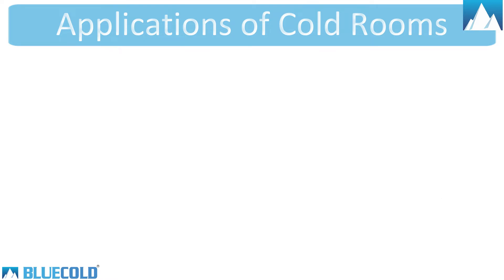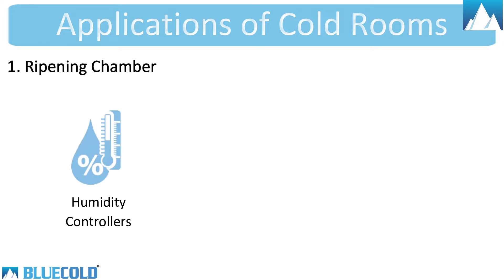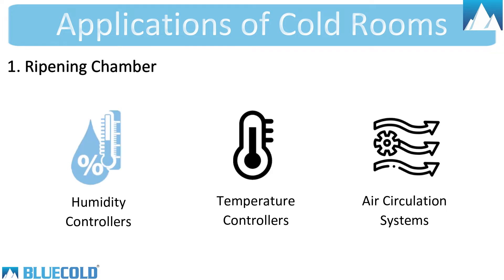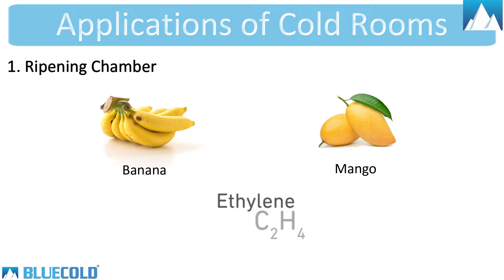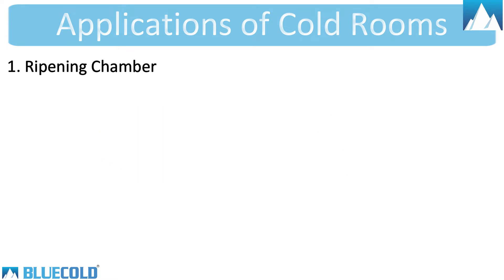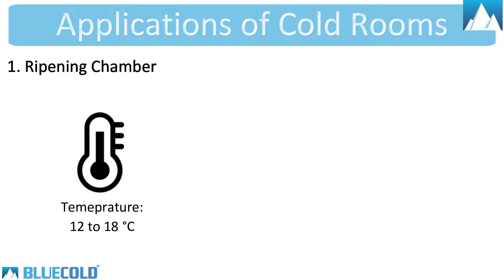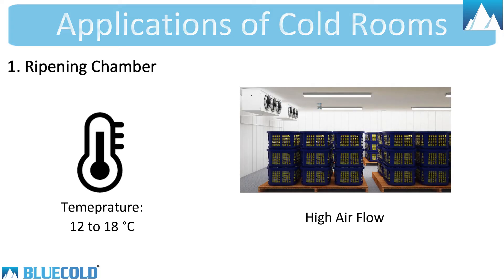Now let's look at different types of applications. 1. Ripening Chamber — it is a chamber equipped with humidity controller, temperature controllers and air circulation systems. Fruits like banana and mango are ripened through the use of ethylene gas generation. They maintain a room temperature of 12 to 18 degrees Celsius and require high airflow.